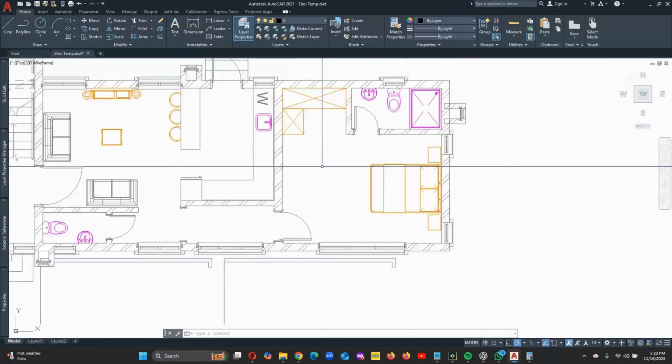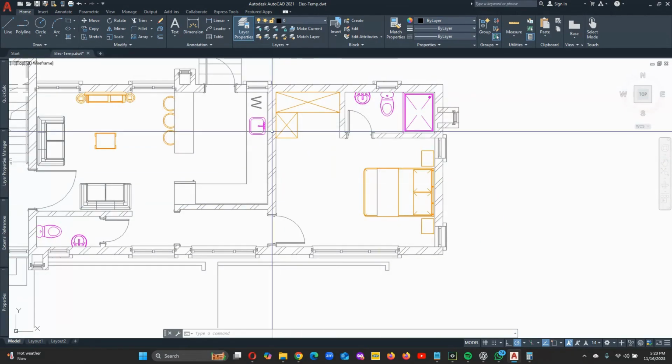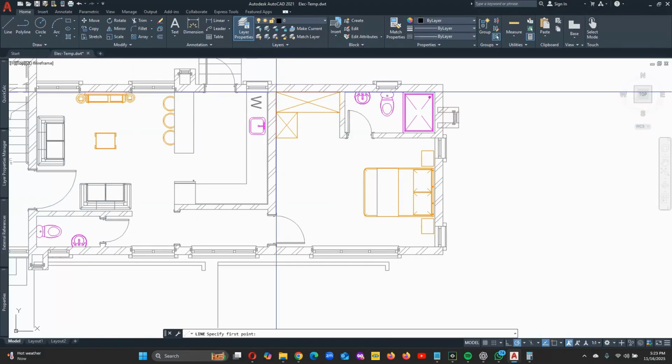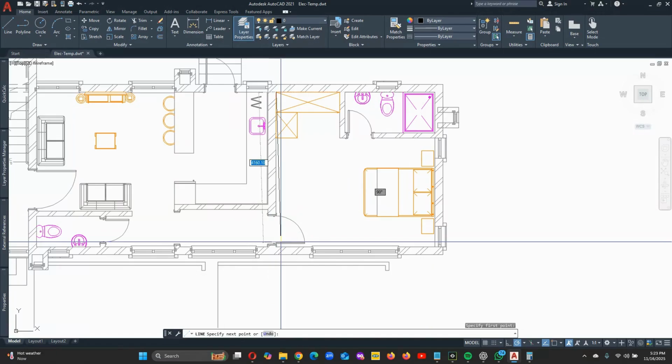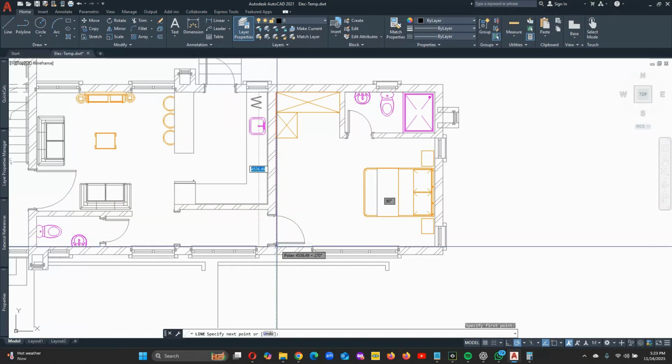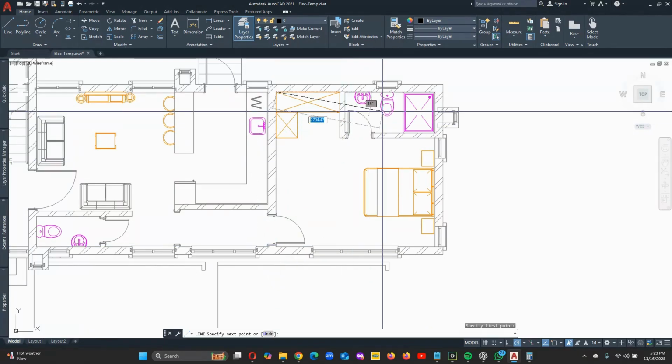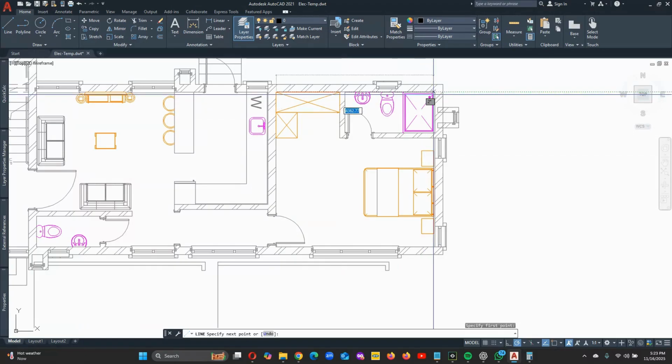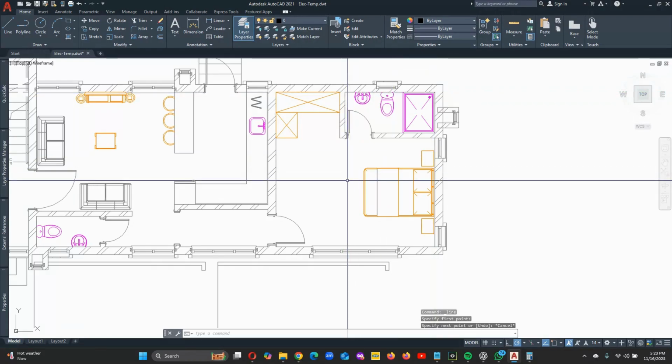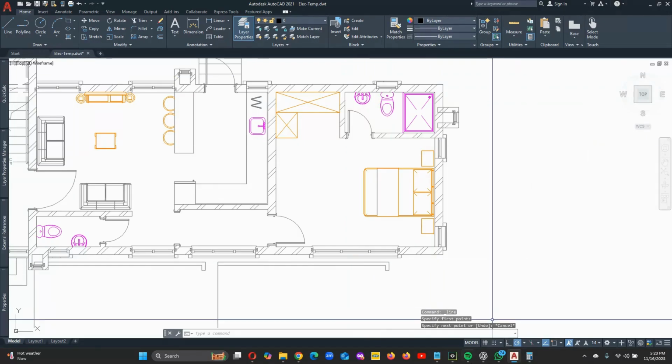All right. So what we normally do is just take the measurement of this bedroom, and the toolkit is going to give us the minimum required illumination for that use case, a bedroom, and for that space using its dimension. So we're having like 4.546. So let's say 4.6 meters by 4.5 meters. That is what we have in this bedroom.